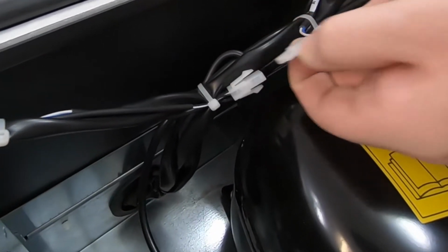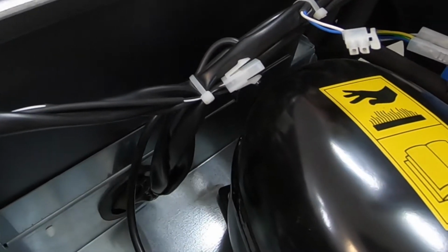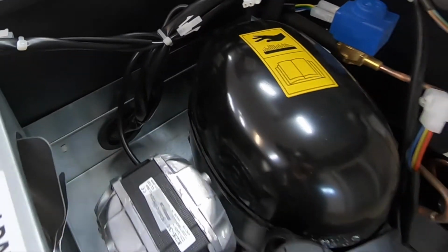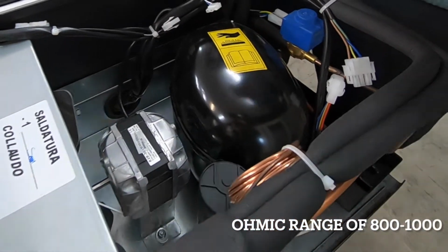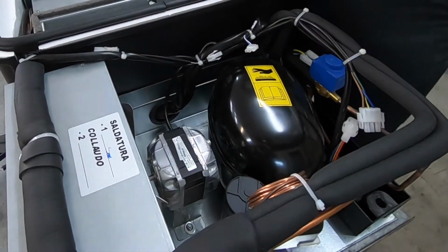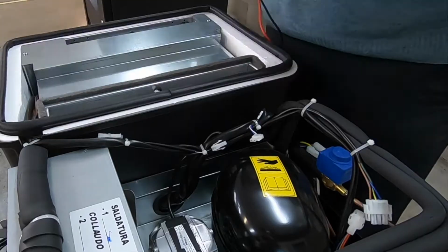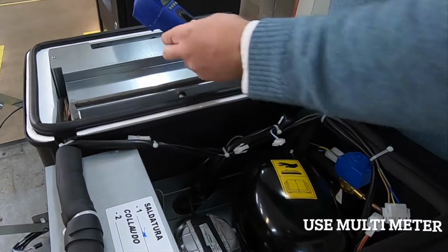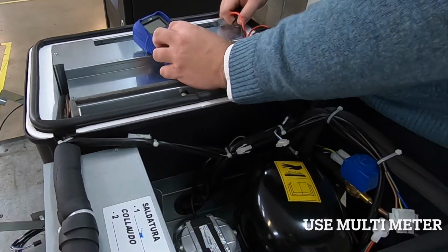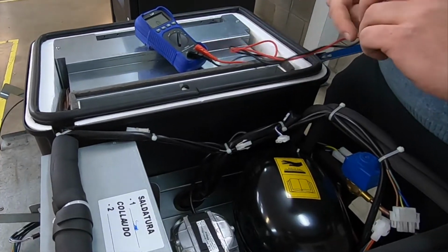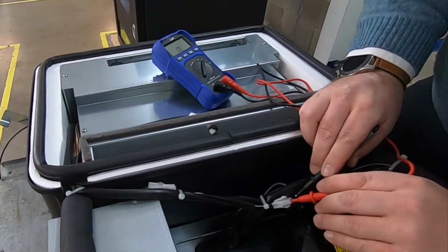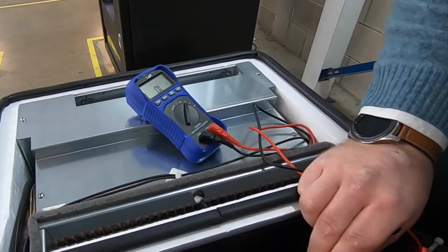If we want to check them, we're looking at an ohmic range between 800 and 1000 - anything in there is a healthy probe, anything out of that range we'll want to look to change it. So we're going to take our multimeter that we looked at in our tools Tech Talk, put it on ohms, and check both points.